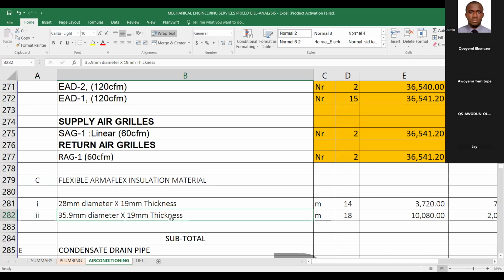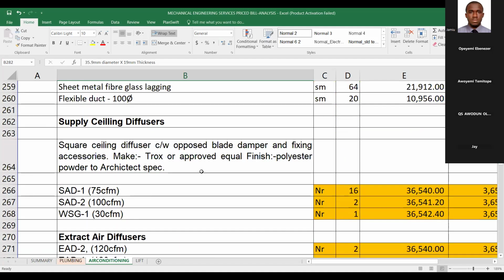This is your Armaflex. The total length of your refrigerant pipe is also the total length of your Armaflex. If your Armaflex is 100 meter, if your refrigerant pipe is 100 meter, now remember that we have different sizes of refrigerant pipe, and each size has its own size of Armaflex. Let's not forget that one Armaflex is 2 meter, or 1.8.